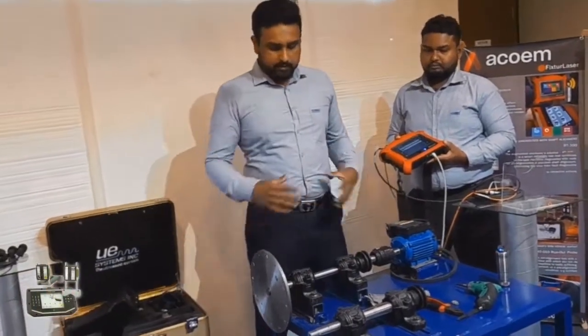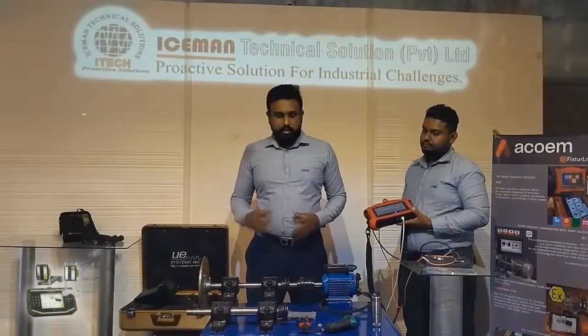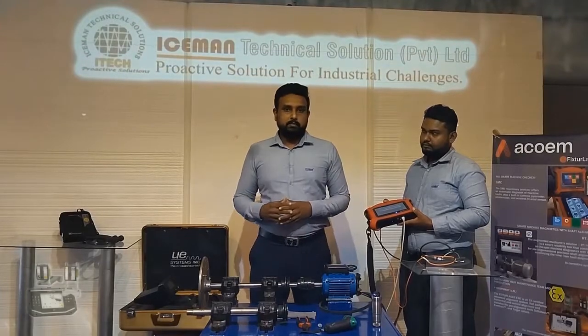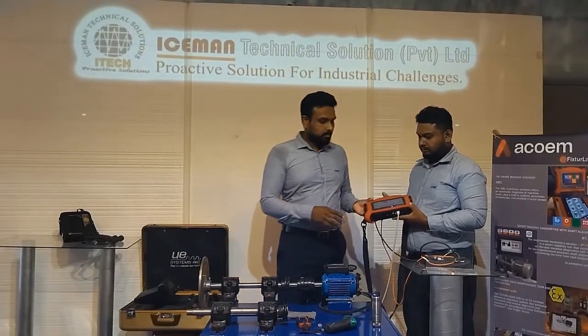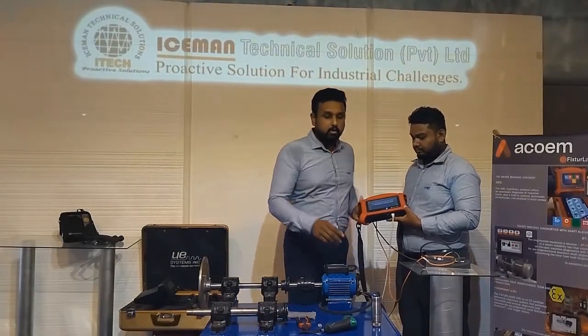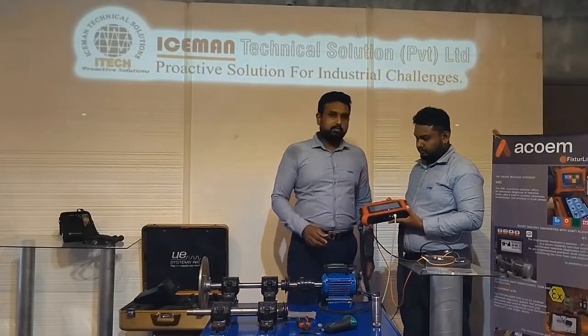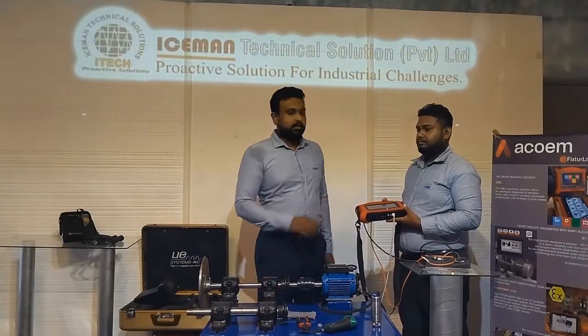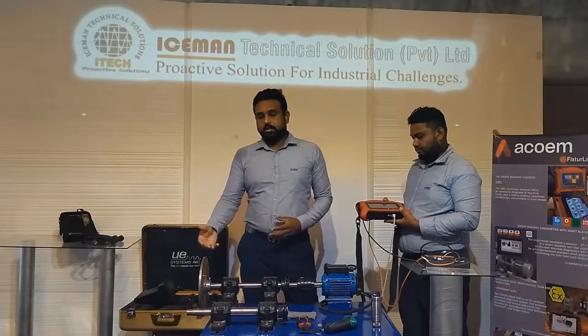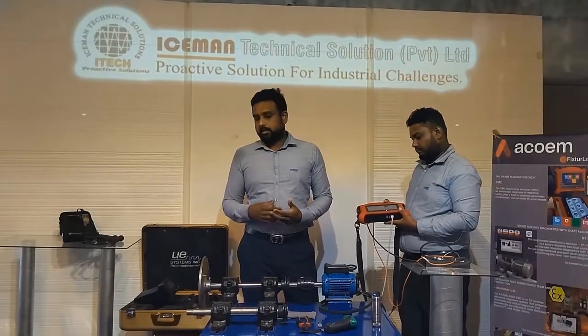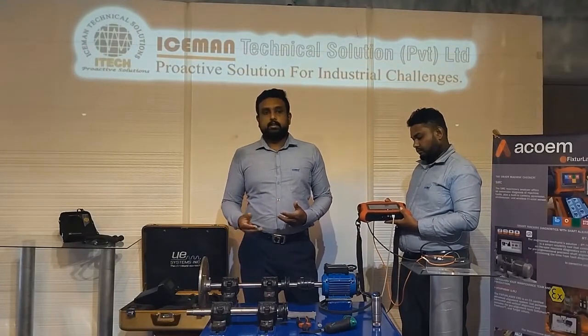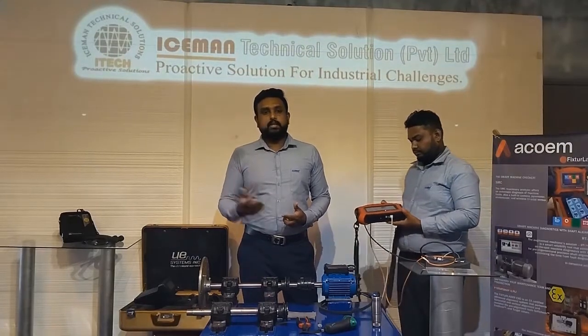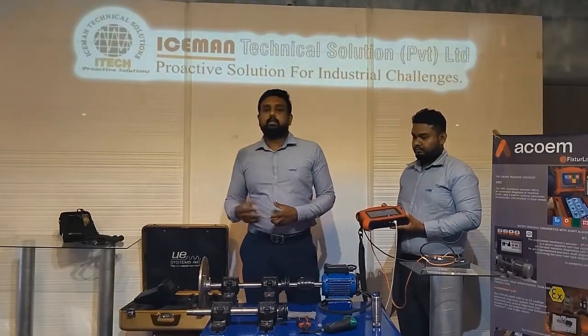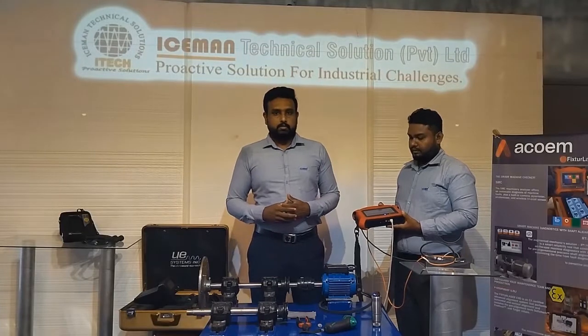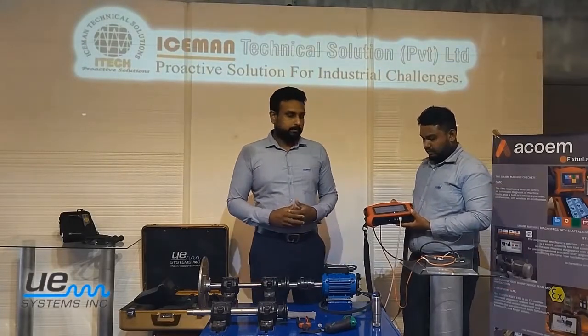Okay, the arrangement is okay. Now we are going to our balancing module. In a vibration tool, there is a special module called the balancing module. In that balancing module, we have to feed some details: the machine impeller weight, impeller diameter, and how many angles we divided. That kind of details we have to feed to the vibration tool.